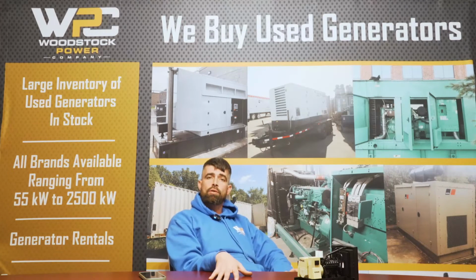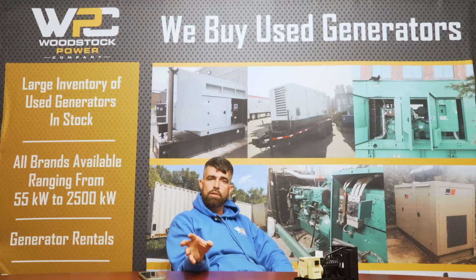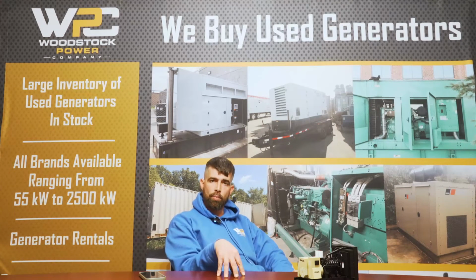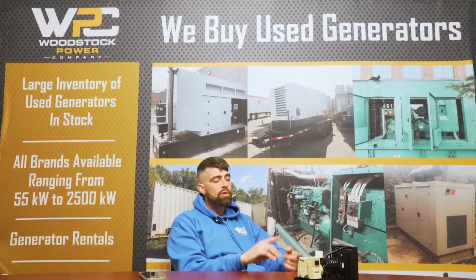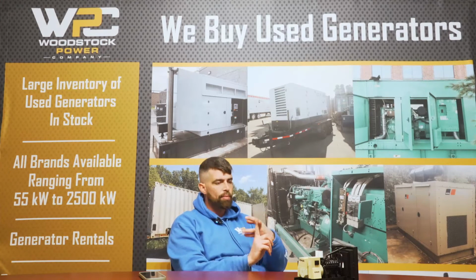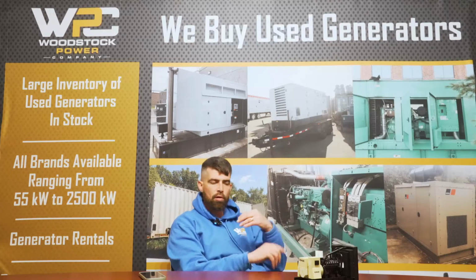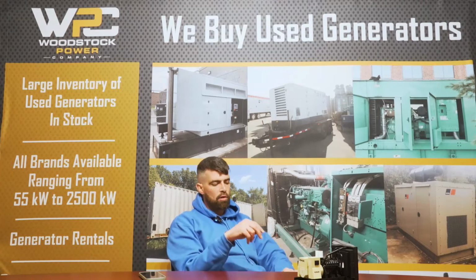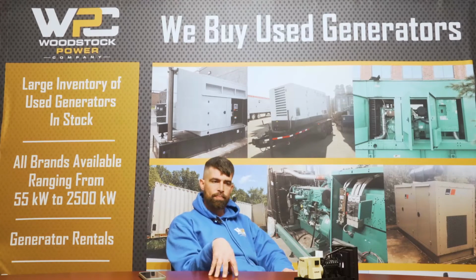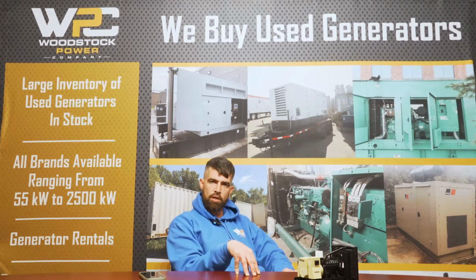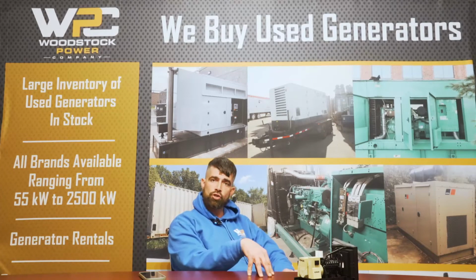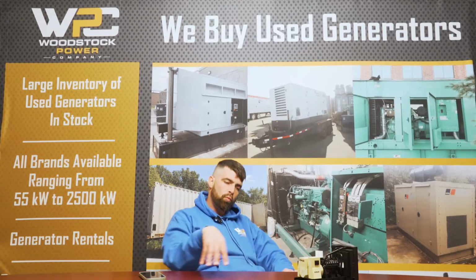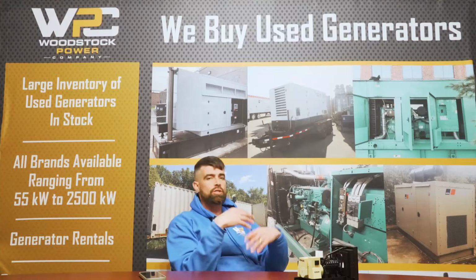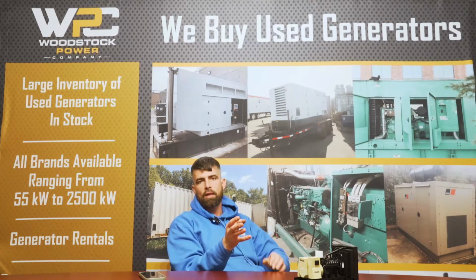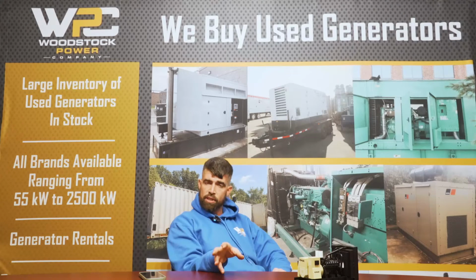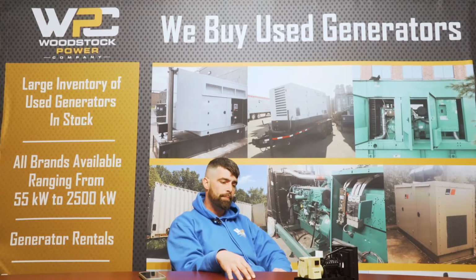Another trick I will tell you, that a lot of service companies use, and it's very simple. Keep a logbook in each generator. Every time you do any service, every time you do any replacement, whether it be batteries, if you're adding coolant, if you're adding oil, if you found a leak, whatever it may be, log the date, the time, and what you saw. That way you're creating a logbook of history on a machine, and it's much easier to detect where an issue started, how it developed from there, and what needs to be done to address that issue versus just going out and starting to guess and check for everything to get to that point. So always keep a log of everything that you find, record it.